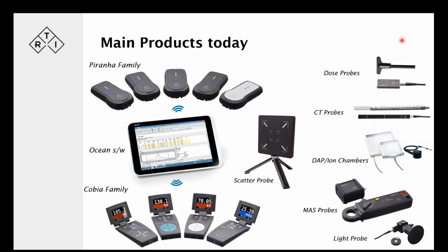So for the Piranha family, we have a number of external probes to capture other data. We've got dose probes, CT probes for CT applications, DAP and ion chamber, where we see DAP chambers becoming more and more popular in the dental field, or dental CBCT. MAS probes, both invasive and a clamp-on for non-invasive measurements of mAs and mA. It clamps on to the high tension cable, cathode side by the tube, and a light probe to check both the ambient light and also the luminescence of the screen. So we have that possibility. So with this, we can then build systems that work well and serve the customers to a large extent.